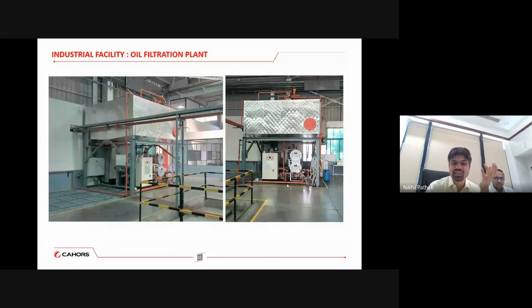Then we have an oil filtration plant in the factory to ensure that all the foreign particles are taken out and the oil is brought to the best of its form with the best BDV value, which is close to 80 kV, and the ppm level we are ensuring is less than 3 ppm in the factory, which is negligibly 0, so that no moisture is left in the oil.